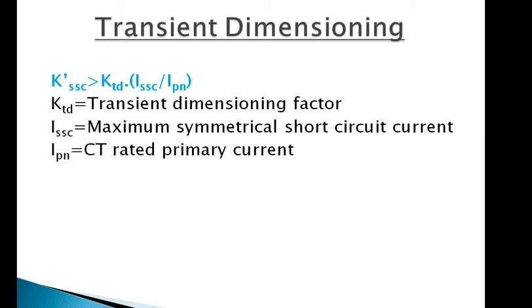Now we will check the IEC equation for the protection CT sizing calculation: K'_ssc > K_td × (I_ssc / I_pn), where K_td is the CT transient dimensioning factor, I_ssc is the maximum symmetrical short circuit current, and I_pn is the CT rated primary current. If the above criteria are fulfilled, then the protection CT sizing is OK.